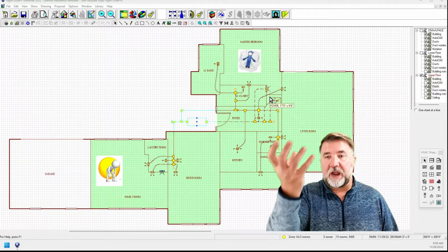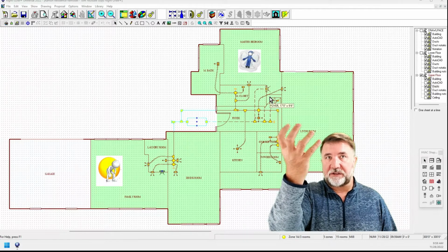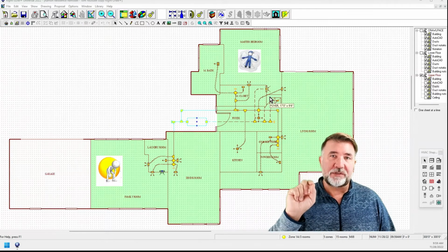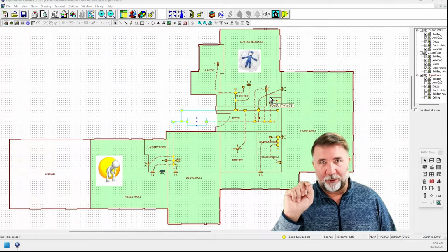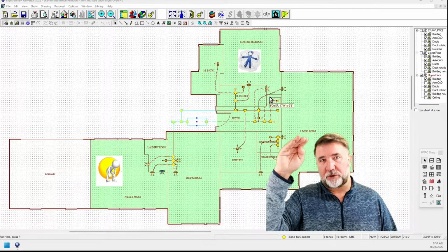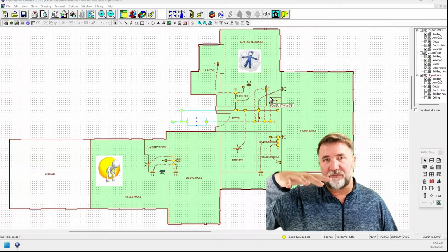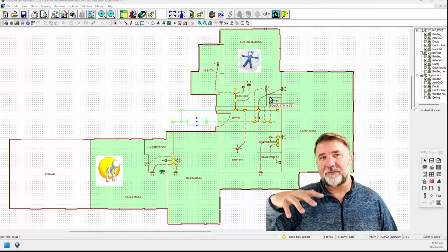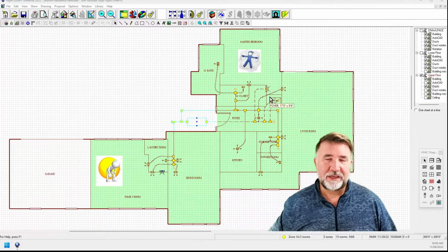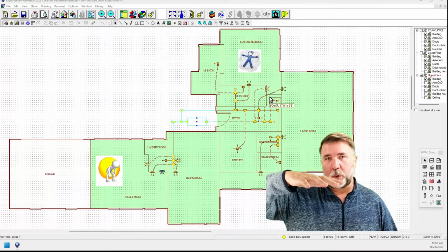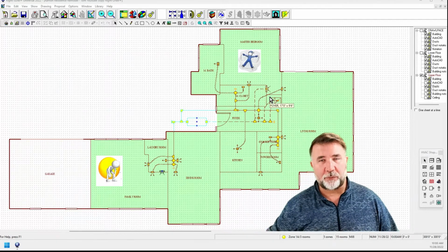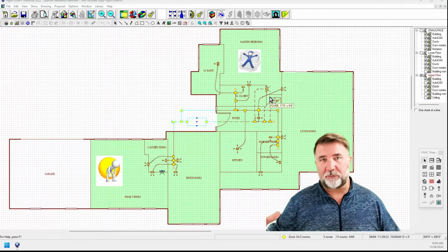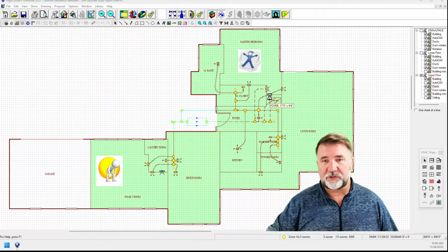So that's where the air is being pulled into the air conditioning system. Now, believe it or not, and we'll have another video on this, returns don't have as much suction power as some people think. If you have a main return like this, I want you to take a piece of paper and see how far away you can take that piece of paper before it gets pulled in to the return. You're going to find 16, 18 inches typically before that piece of paper just has no suction at all and it just falls. So you get a visual of that. It's not that I'm going to create this giant vacuum in the return. And again, we'll talk about that in a different video.